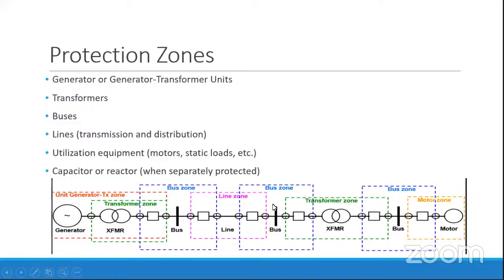Then the transformer zone should also provide backup protection to this busbar. Then, with this local fault protection, another primary protection should be given to this transformer. Likewise, from downstream to upstream, we need to divide certain zones for protection equipment.